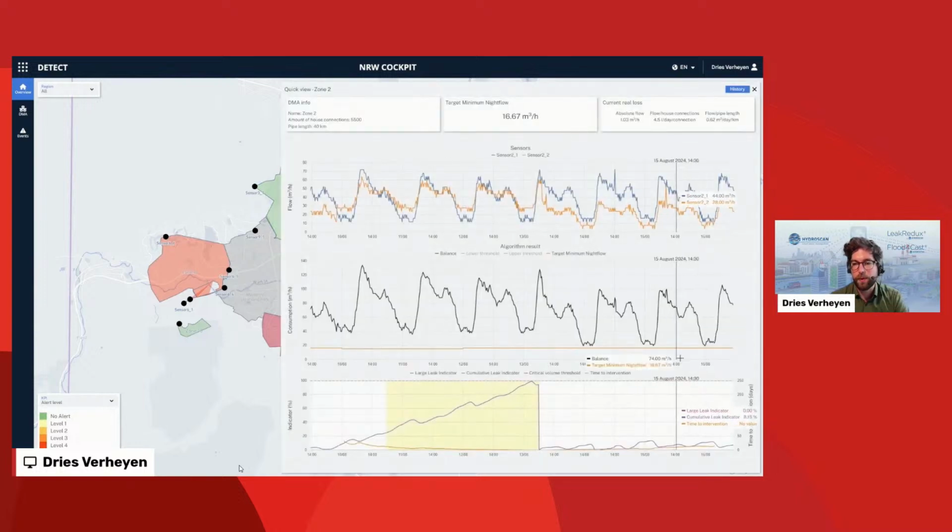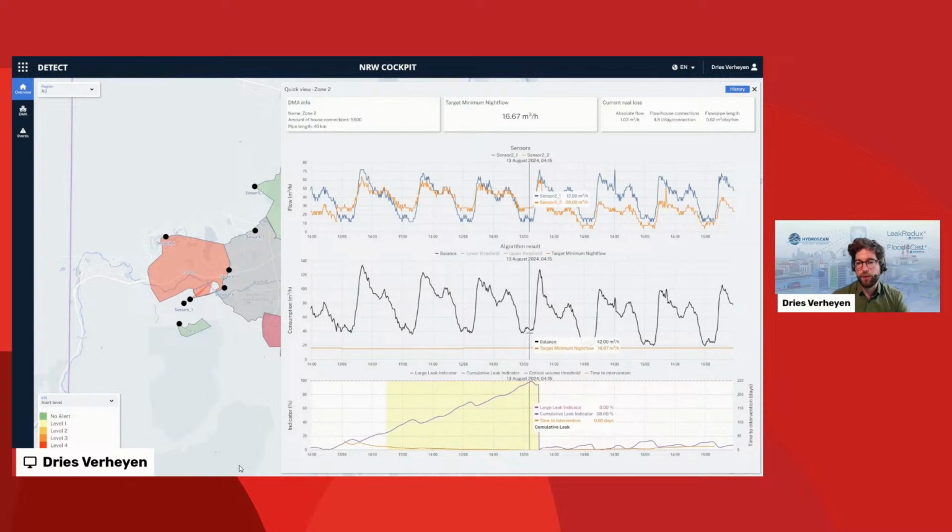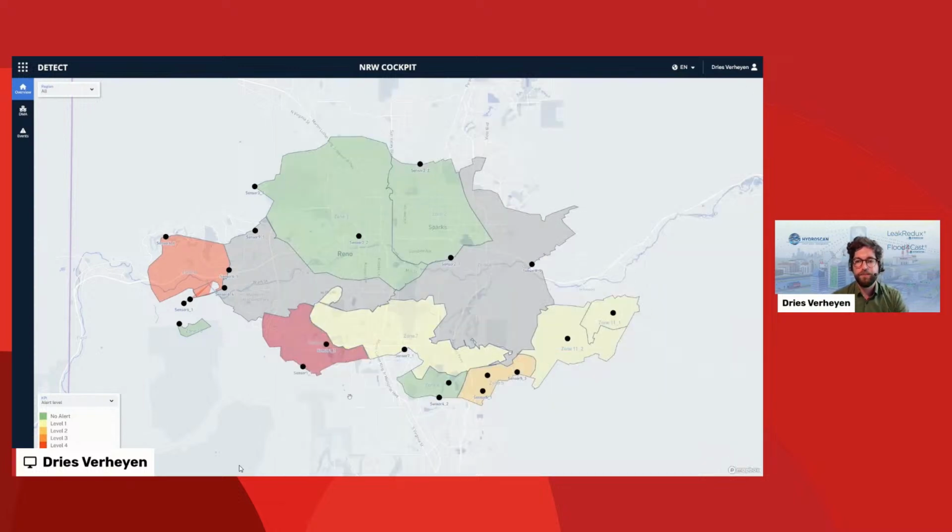And then we have also this green. I will show you some. There you see that last week they have found the leakage there. So on the bottom you see cumulatively some leaks were rising. People were sent on the terrain, found the leak, repaired it. So this is again back to normal, I would say.